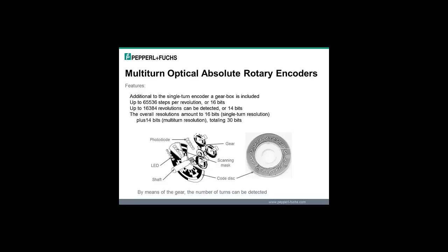The multi-turn optical absolute rotary encoders are used for applications that need to know a unique position over multiple turns. A set of gears that are in the encoder keep track of the number of complete turns. The gears allow 12 bits, which is standard, to 14 bits or 16,384 number of turns without repeating. With the maximum resolution per turn of 16 bits and the maximum number of turns, which is 14 bits, you can have an encoder with 30 bits of information, which will meet most application needs.